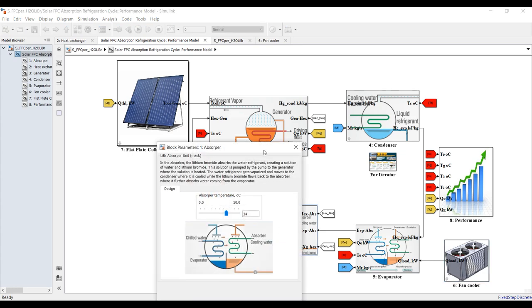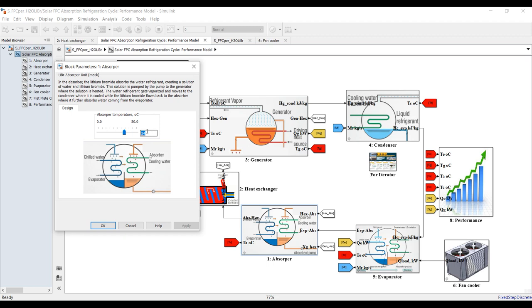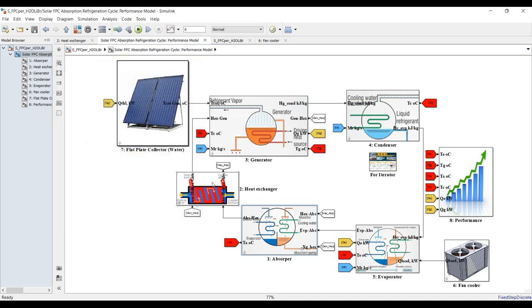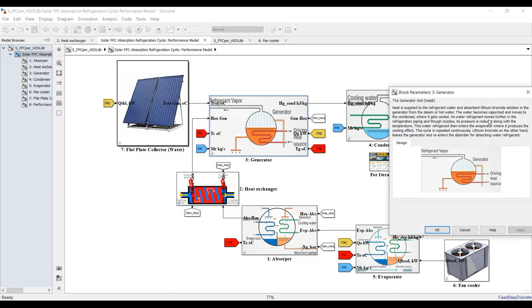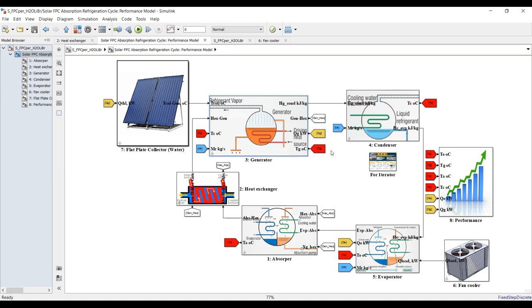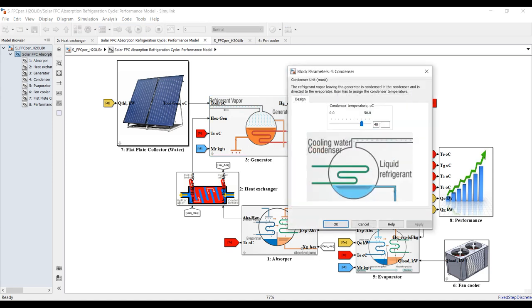Let's begin assigning parameters. For the absorber unit, we need to assign the absorber temperature. Based on my experience and previous research articles, you should assign it between 30 and 35-36 degrees Celsius. For the heat exchanger, we just need the effectiveness — I will keep it at 80 percent. For the generator, we don't need to assign anything. For the condenser, we need the condensation temperature: 40-45 degrees Celsius.